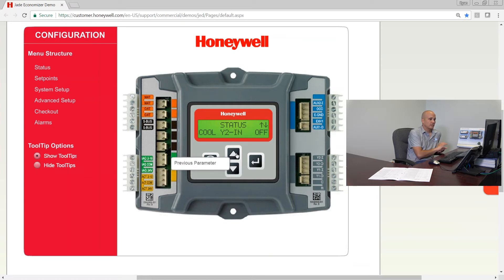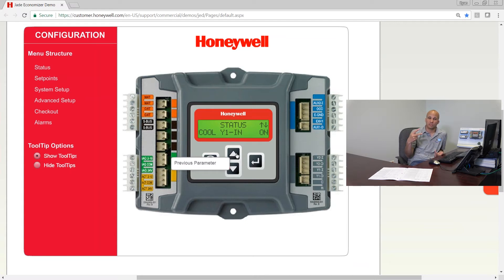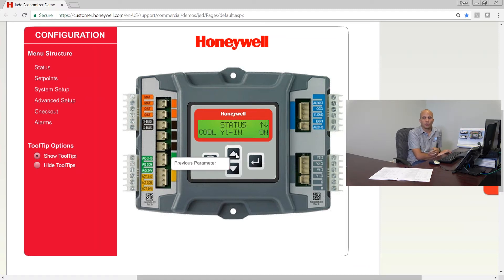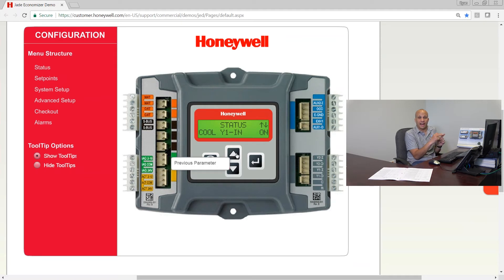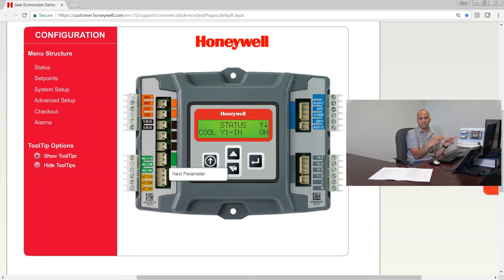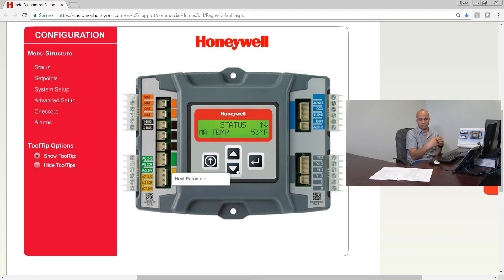Next I want to see the screen with cool Y1 in, cool Y1 out, cool Y2 in, and cool Y2 out. The 'ins' are my thermostat signals coming into my economizer controller, and my 'outs' are my economizer controller going to my compressor. You normally will not have Y1 in and out matching, nor Y2 in and out matching. Y1 comes in and either becomes my economizer output or my Y1 output if it's not an economizer day. When Y2 comes in from the thermostat, it'll either be my Y1 output calling for compressor if it's an economizer day, or Y2 output if it's not.